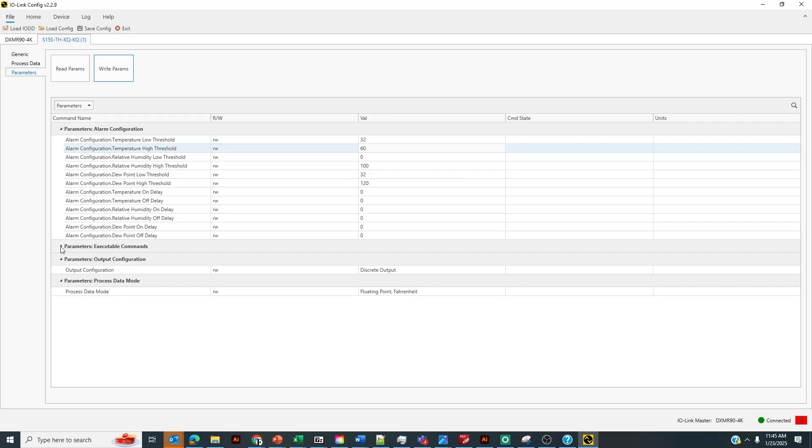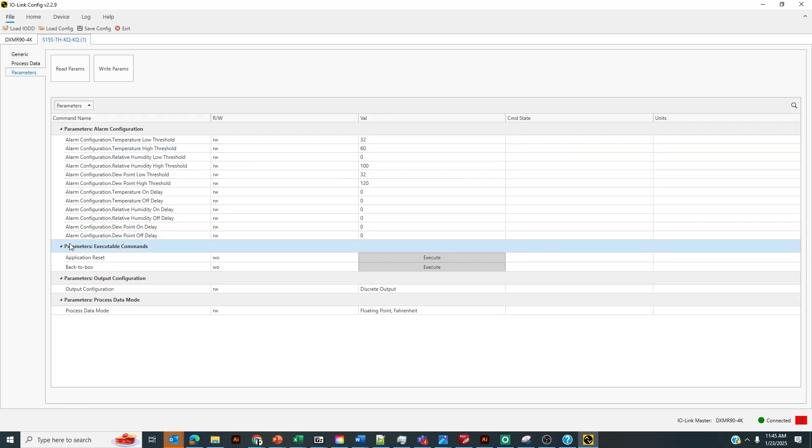We could also, if you want to turn the device to factory default settings, do an Application Reset. This will restore the sensor to factory default settings while retaining communication to the IO-Link master. This is what I typically recommend for setting the device to factory default settings. If you select Back to Box, that'll restore the device back to factory default settings, but you will lose communication to the IO-Link device.